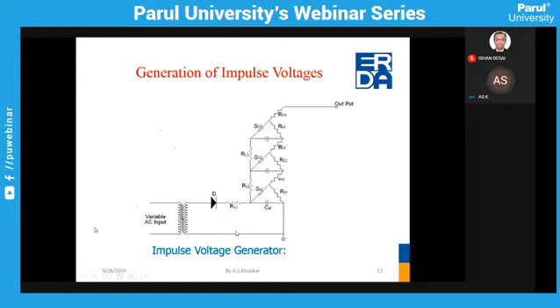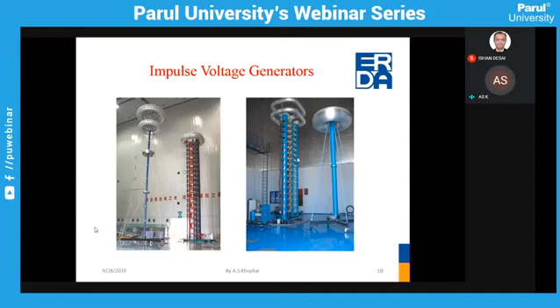And here is one more picture I have added, which is a rating of 3000 kV impulse voltage generator and 3000 kV voltage divider. These voltage dividers are used for the measurement of the test voltage, and this impulse voltage generator is used to generate the lightning impulses in the laboratory, as well as the same source can be used to generate the switching impulse in the laboratory.